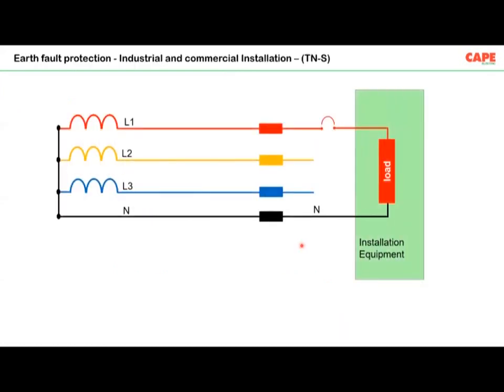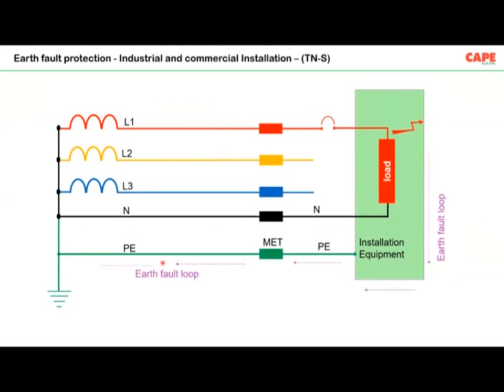For high-rise buildings, for industrial and commercial installations, we are supposed to have a network called TNS, which is basically a five-wire system. In a TNS system, imagine there is a fault. The fault return is happening through the protective conductor, and this is the way the fault loop, the dotted lines, you can see the fault loop circuit. The impedance of the circuit ensures whether the protective device is able to trip or not. So basically, earthing is all about making this impedance as low as possible.